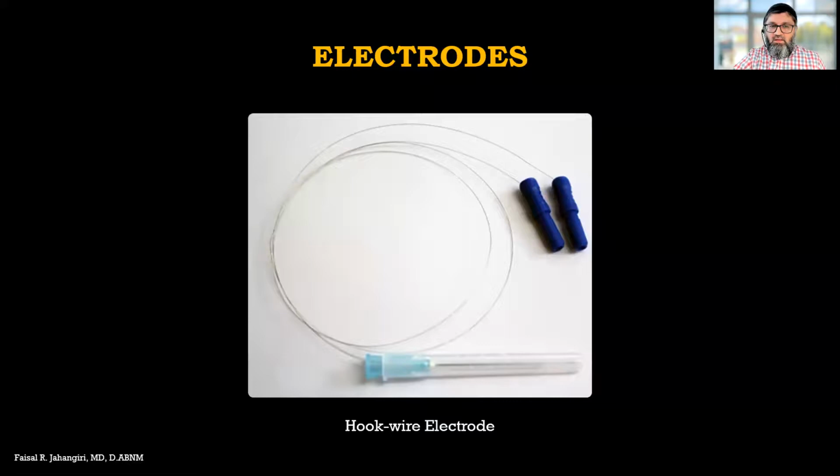It is highly recommended for cranial nerve recording, for vocal cord recording, from the soft palate, tongue, and facial nerve. Hook wire is the first option for cranial nerve recording, because you can put two hook wires and have very low impedance and very high specificity for the nerve. The common mode rejection is also better on this one.